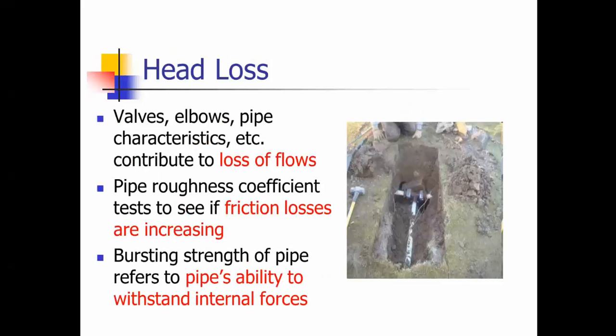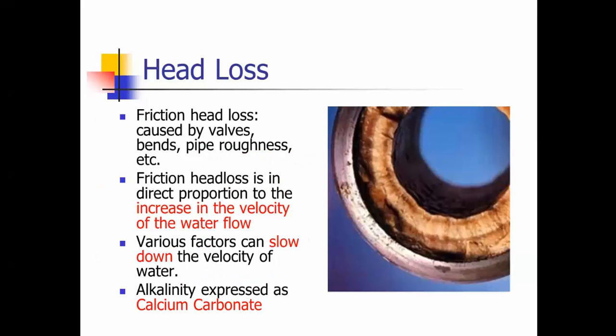Head loss is your loss of flow across elbows and pipe. Roughness of the pipe is a consideration. If you see coefficient tests, if friction losses are increasing, the bursting strength of the pipe refers to the pipe's ability to withstand the internal forces. Head loss, friction head loss, is caused by valves and pipe roughness. It can also be caused by scaling, like in this picture. The head loss is in direct proportion to the increased velocity of the water flow. And there are different factors that can slow down the velocity of the water.